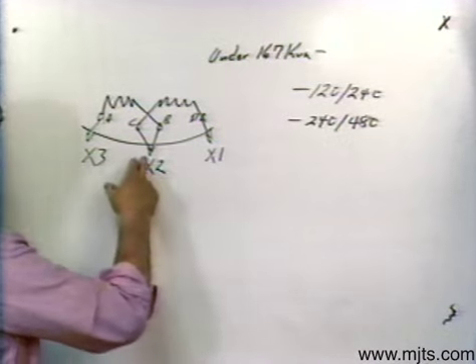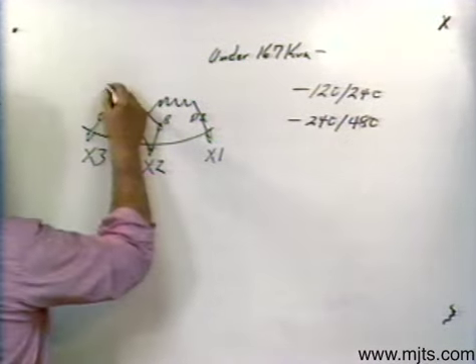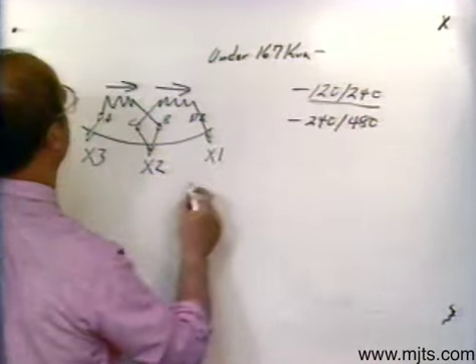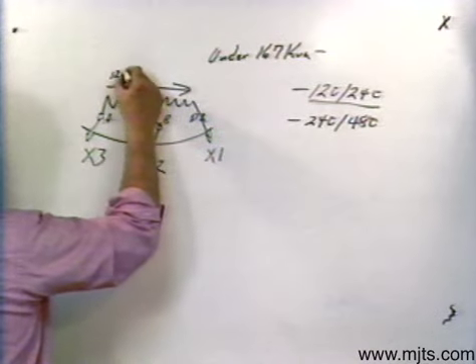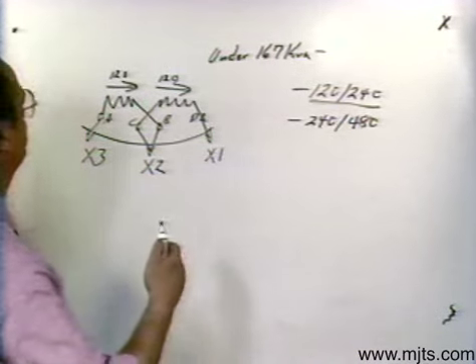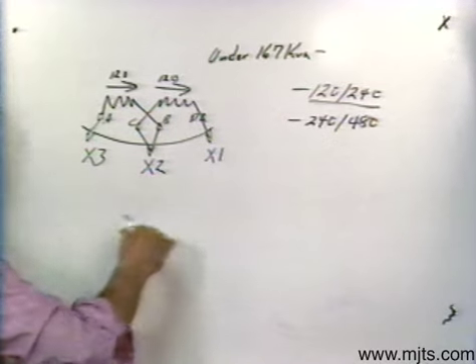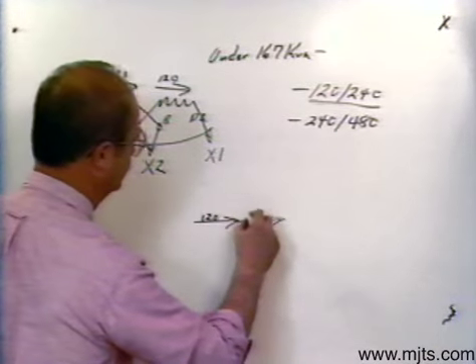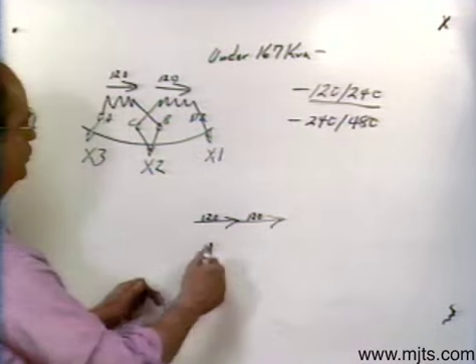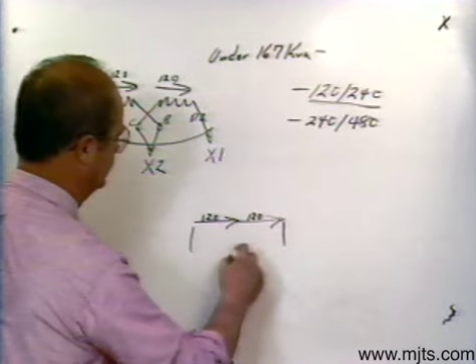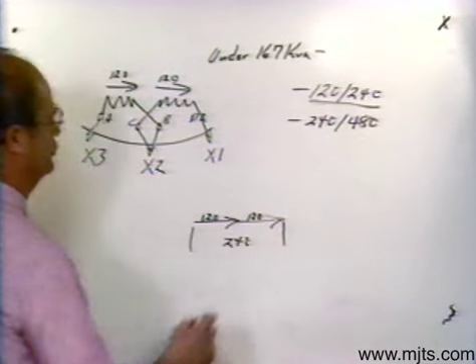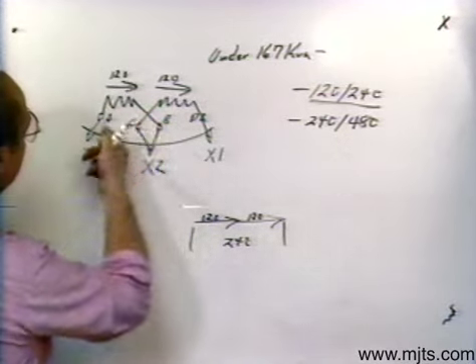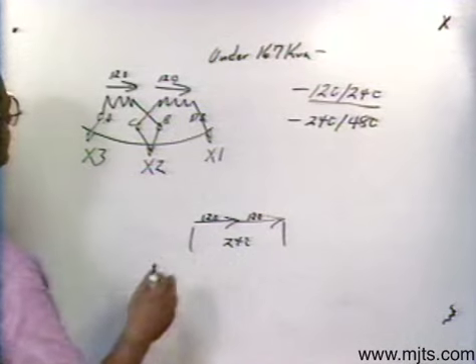If I draw voltage vectors representing the voltage value — let's say each one of those vectors represents 120 volts — when we series connect vectors we go head to tail. If each vector represents 120 volts, then all the way across you would have 240 volts. The tails are crossed over for convenience in paralleling, as I'll show you in a little bit.